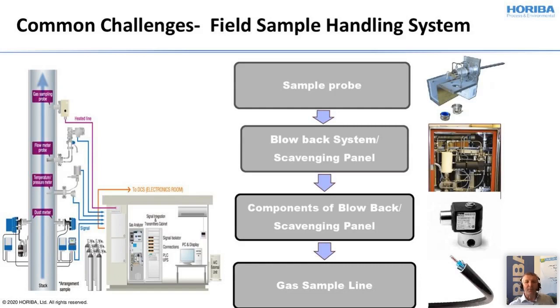Sample probe, the first topic from the stack. The sample probe filter frequently gets choked. There might be several reasons for this. One is an improper selection of the filter micron size by the engineering company. Unfortunately, this happens even with good engineering companies due to insufficient information on gas sample parameters from the customer side. Another reason might be selecting the wrong material for the filter. The reason again comes from unknown sample conditions to the planning engineers.